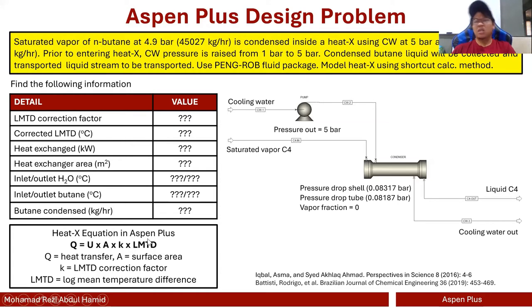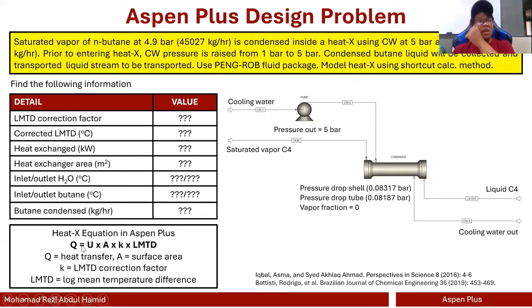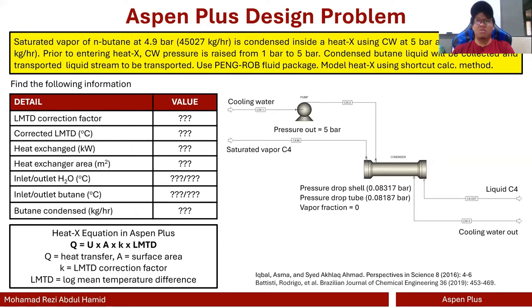The LMTD represents a driving force for heat transfer — the bigger the LMTD, the higher the heat transfer. K is a factor that describes the geometric effect of the heat exchanger that may affect the overall LMTD. A is surface area, and U is the heat transfer coefficient. You can have a clean U value and a dirty U value, because fouling effects need to be accounted for. However, in the shortcut calculation method, Aspen Plus does not have the option to include fouling factors. That feature is available in the design or detailed calculation modes.